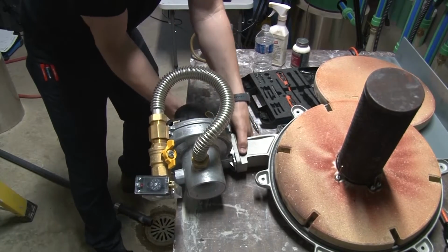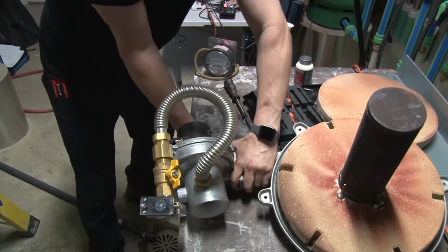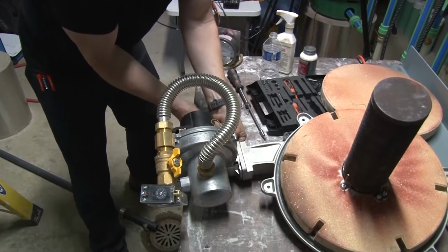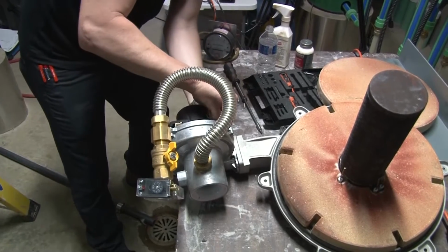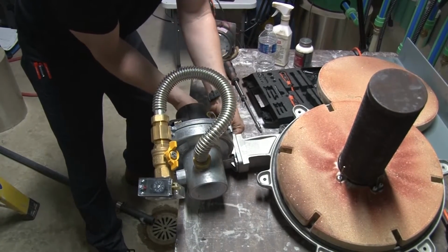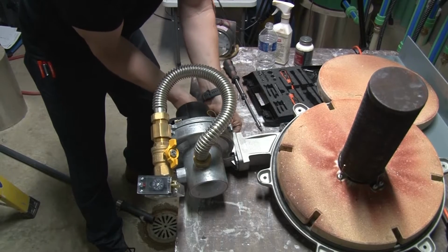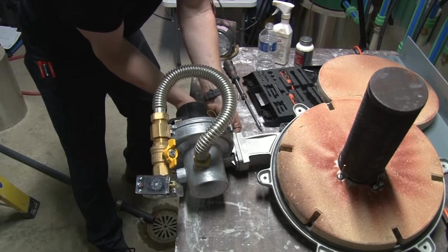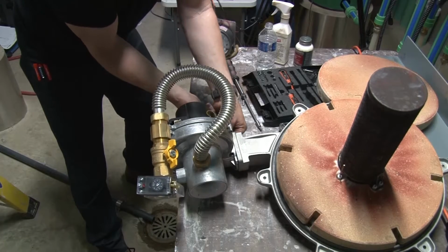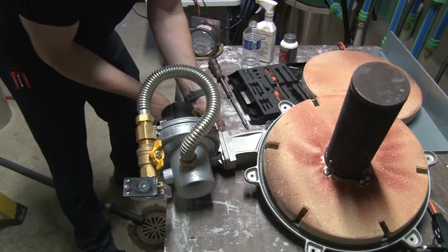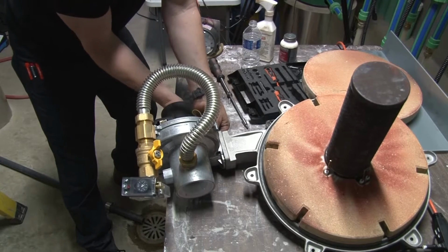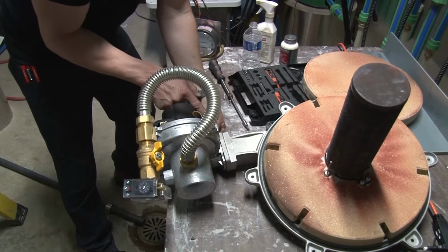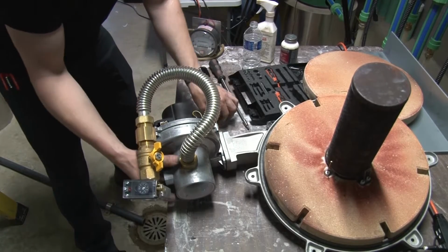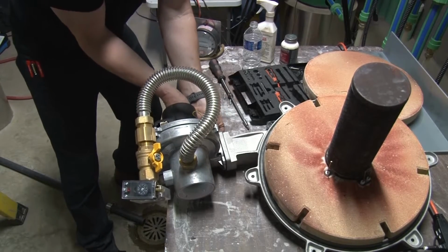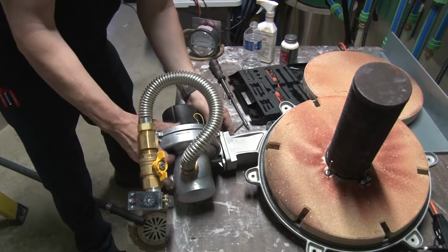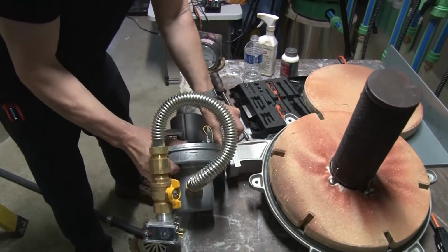It's a 4 millimeter Allen key in there that we got to get. I'm just going to crack this guy. There we go. And we'll have a look at this little flapper. The purpose of it, why it's actually in there, is these boilers are also approved for common venting. So instead of having multiple vents out the boiler for whatever reason, I can basically only have one single vent. I can put up to 4 of these boilers on one vent system, and this little flapper protects this boiler when there is no burner firing in this boiler, but the other boilers are firing, from that flue gas backing into this particular boiler's heat exchanger.